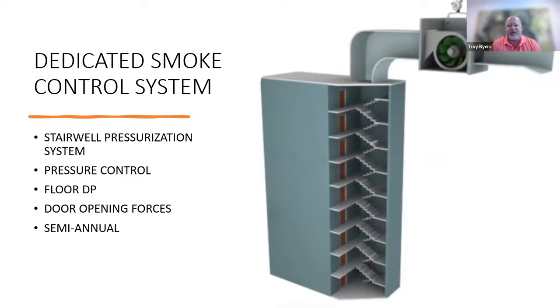There's going to be a component of pressure control, because the whole idea is to maintain pressurization in this stairwell. So you might have pressure sensors, a VFD on the fan, and some barometric relief dampers or something like that. We need to understand all of the components of the system to properly document settings and operating characteristics.